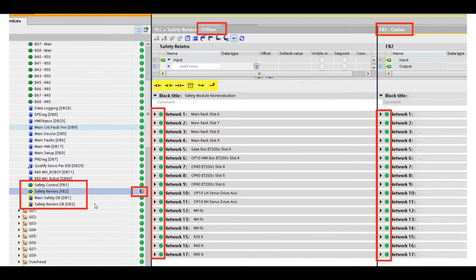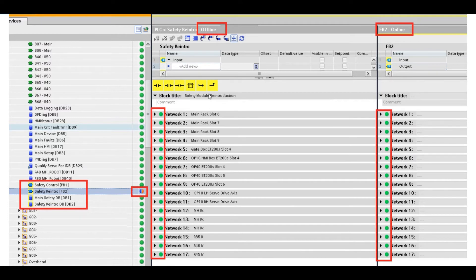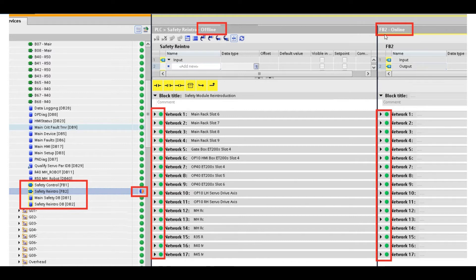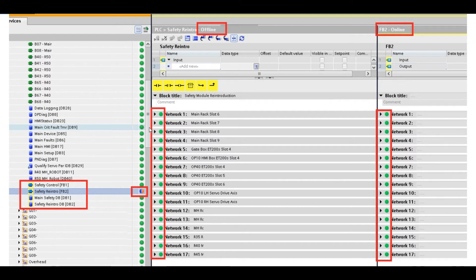The thing is, once you double click this safety program, basically that is a read-only mode. You go online, and you know the TIA Portal platform has a function to online compare the offline with the online difference. Once we go offline and online compare, it shows all the logic, they all match.